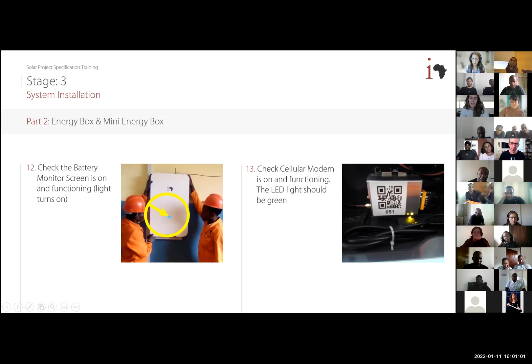Now, after checking all the components of the energy box and confirming the cellular modem is sending data, we need to check that the phone application is receiving the data and we're getting good readings from the system. Go to project management, check monitoring unit, write the project name - it should already be registered on the web or phone application - then open the project. You'll see the last readings of energy and voltage, since we are now also reading voltage values for each project.